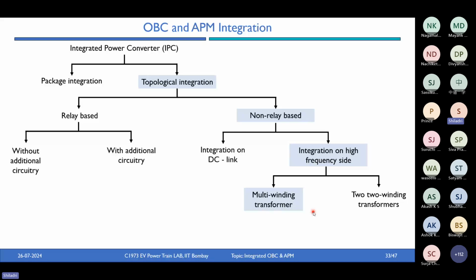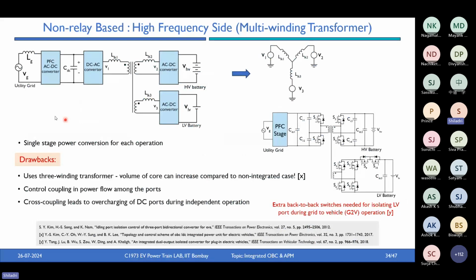The multi-winding transformer idea is simple: you have a three winding transformer, with a bridge here, a bridge here, and a bridge here—full bridges—all coupled using the three winding transformer. The equivalent circuit looks something like this: you have high frequency AC sources, and by changing the phase shift between each one, you can control power flow between any one of the three ports.